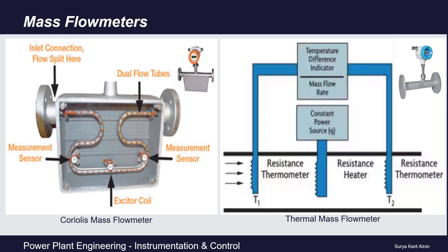A Coriolis mass flow meter works using the inertia caused by the fluid flowing through oscillating tubes. Fluid enters on one side, passes through the tubes, and exits the other side. The fluid exerts pressure on the tubes, causing them to vibrate. This vibration is excited by an exciter coil and measured by two measurement sensors. The inertia causes the tubes to twist in proportion to the mass flow rate, and this twisting is measured with sensors to generate a linear flow signal.